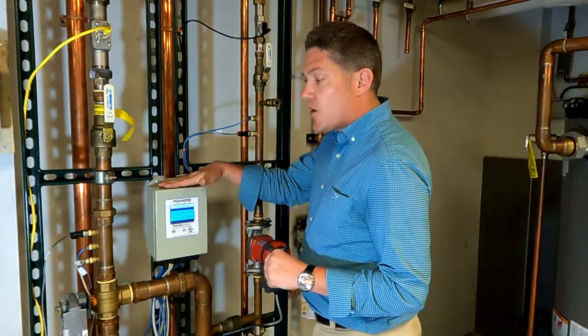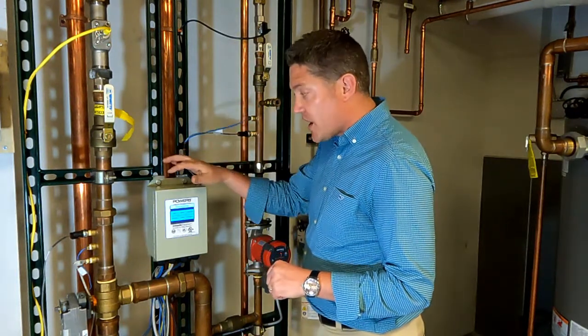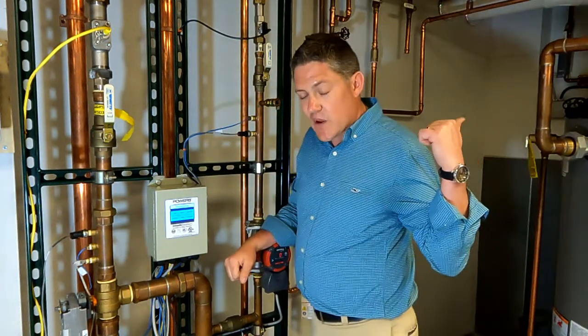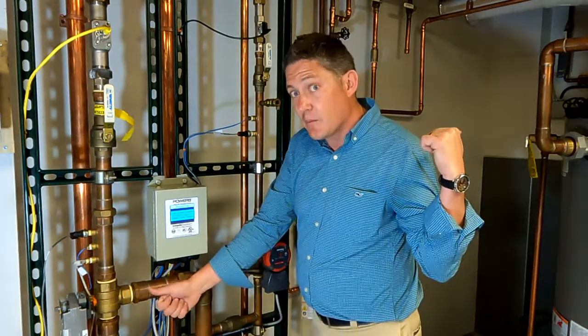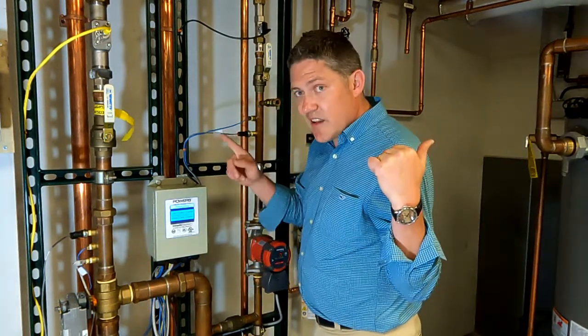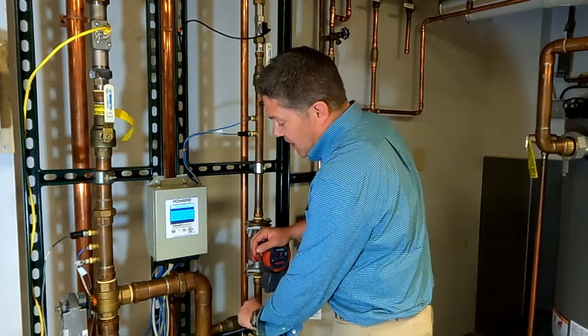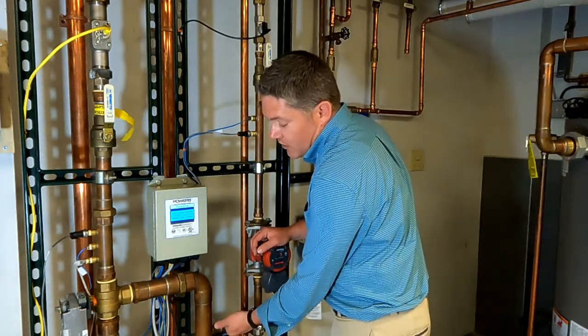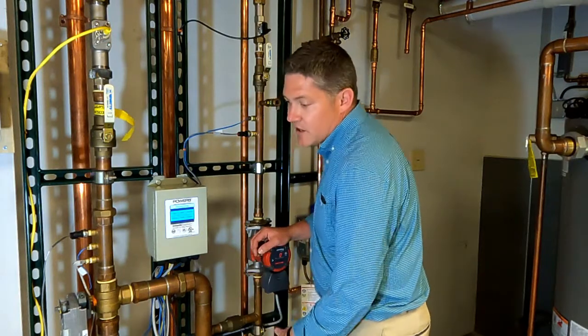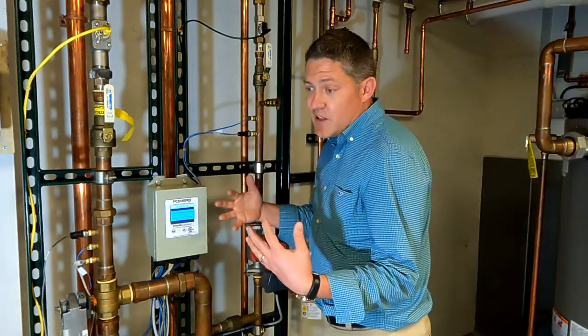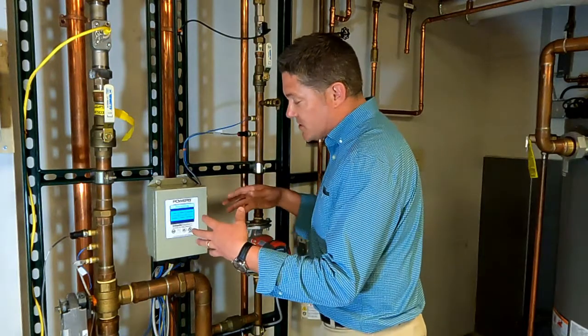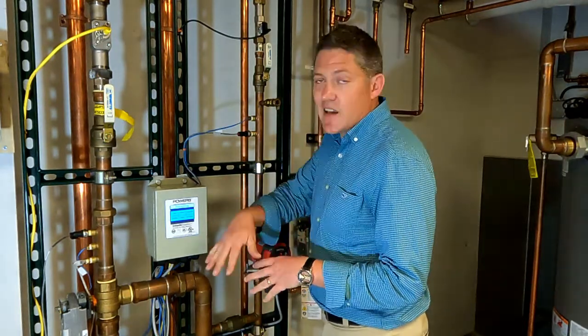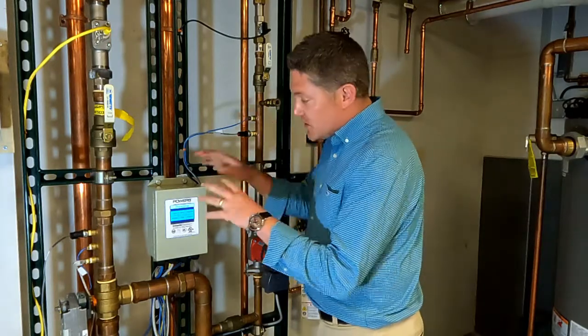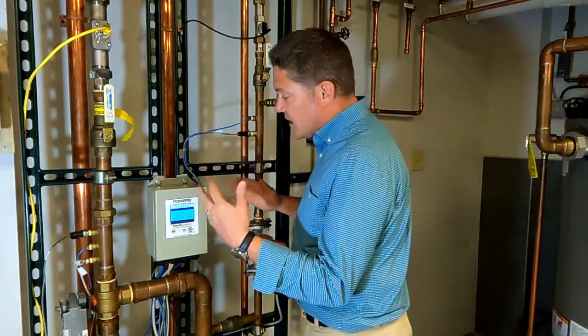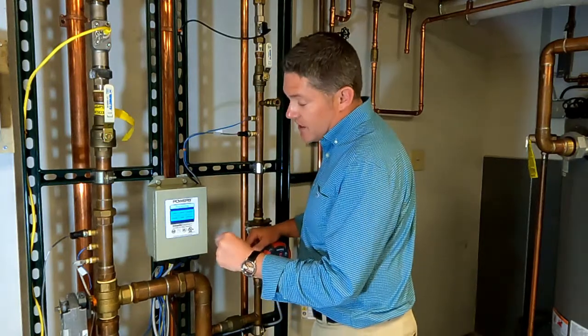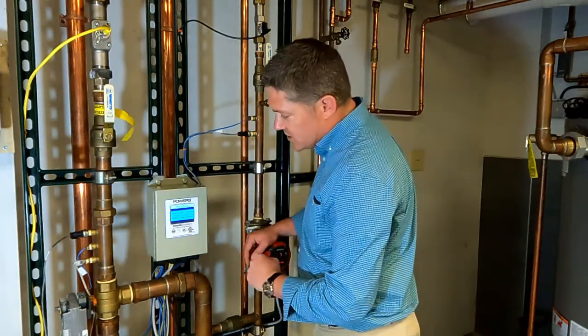You basically have to try to raise the temperature to the highest point of the actual mixing valve. Probably going to have to raise your supply temperature significantly above that desired recirc sanitation mode temperature. And you're probably going to have to open your ball valve on the balancing valve wide open. And then once everything is done and you've completed your sanitization mode on thermostatic, then you're going to have to reset the entire valve, rebalance it, reset your heat source. And so it's a very complicated process with thermostatic, very easy on digital.